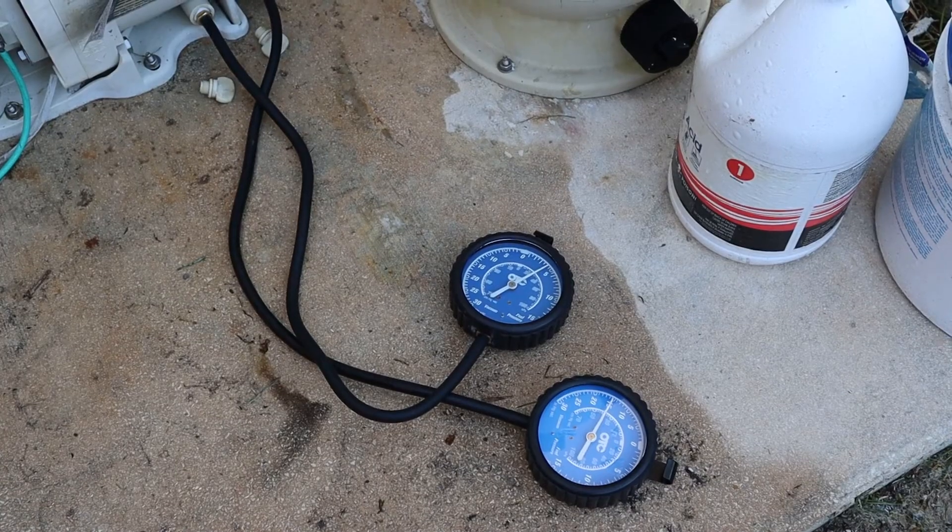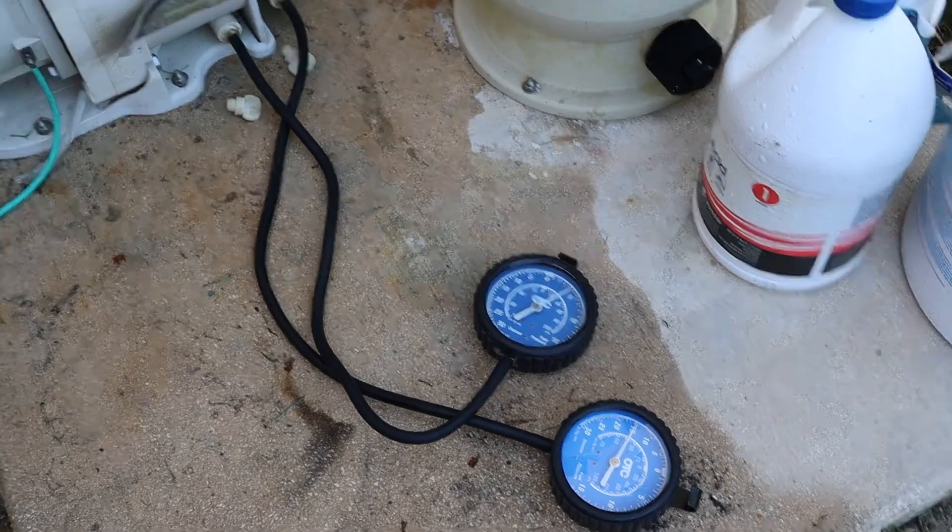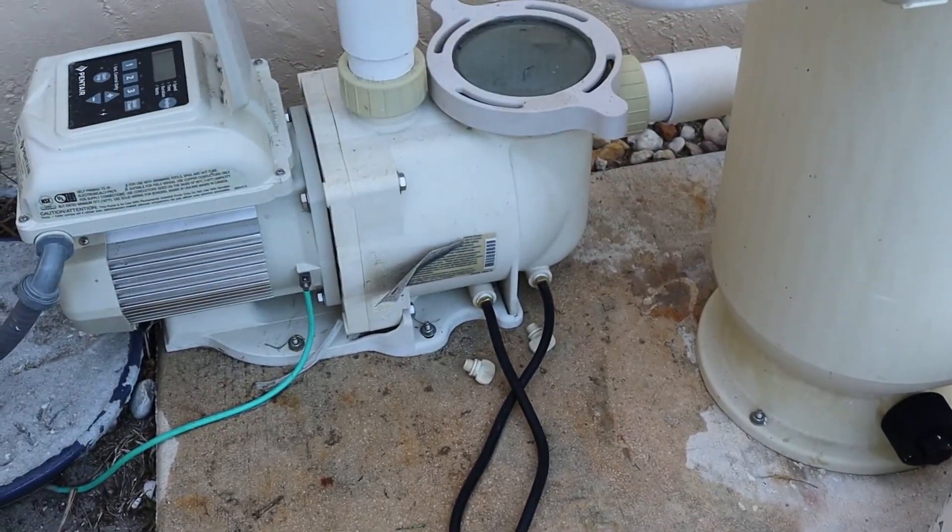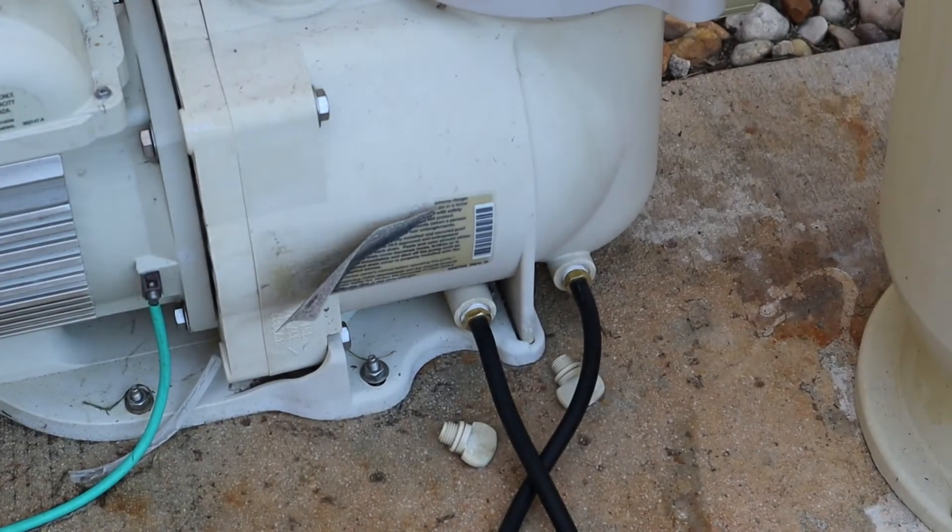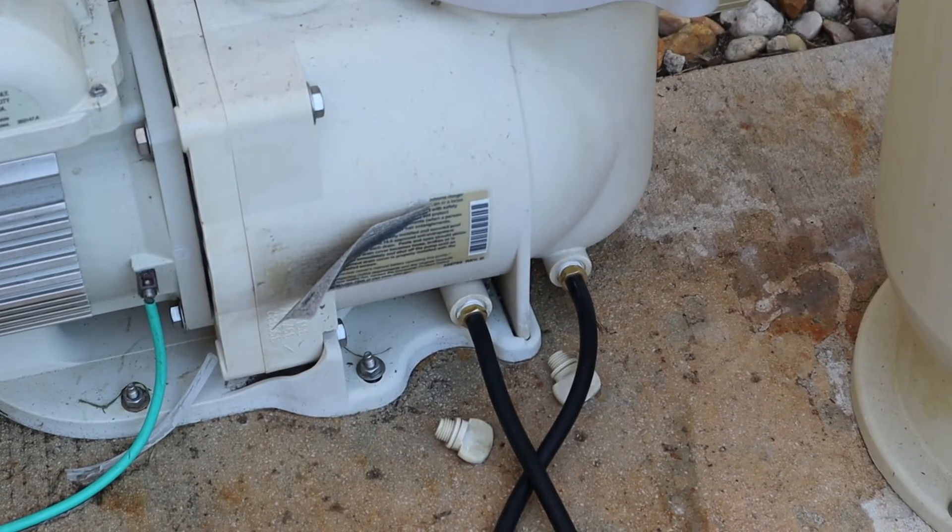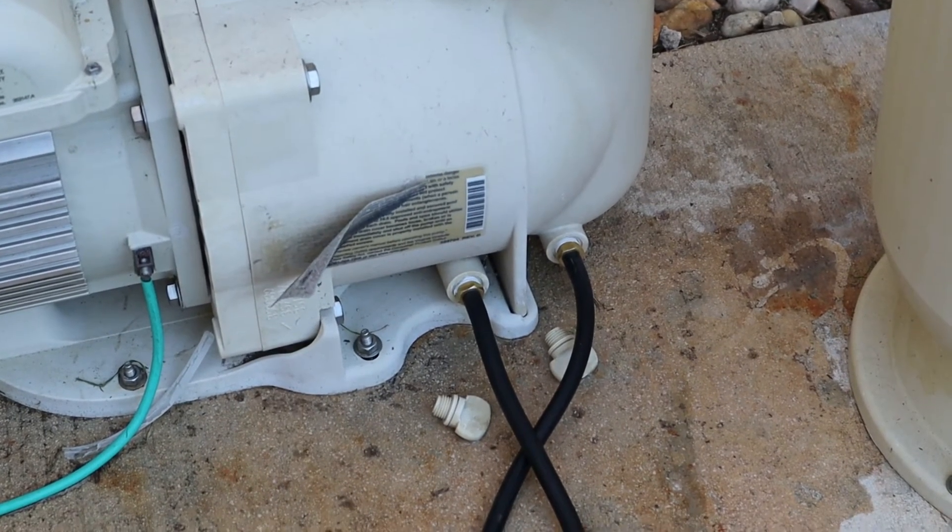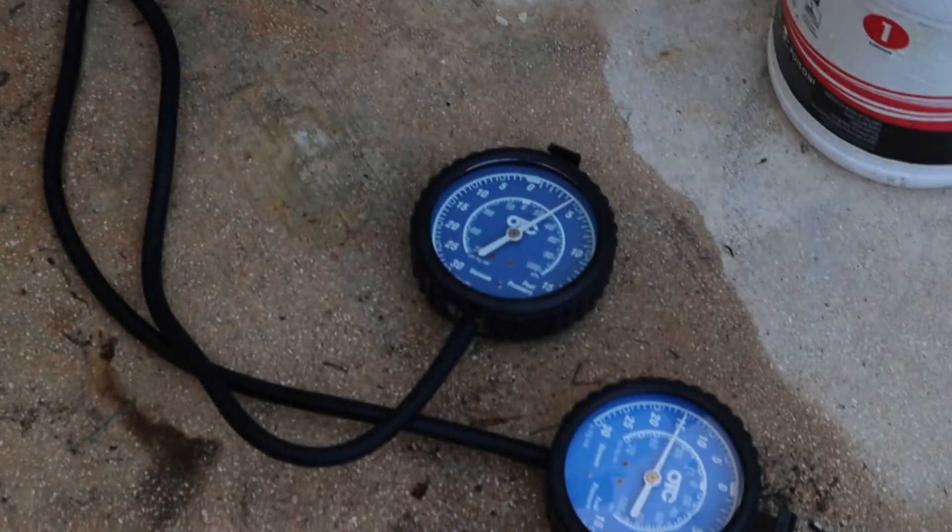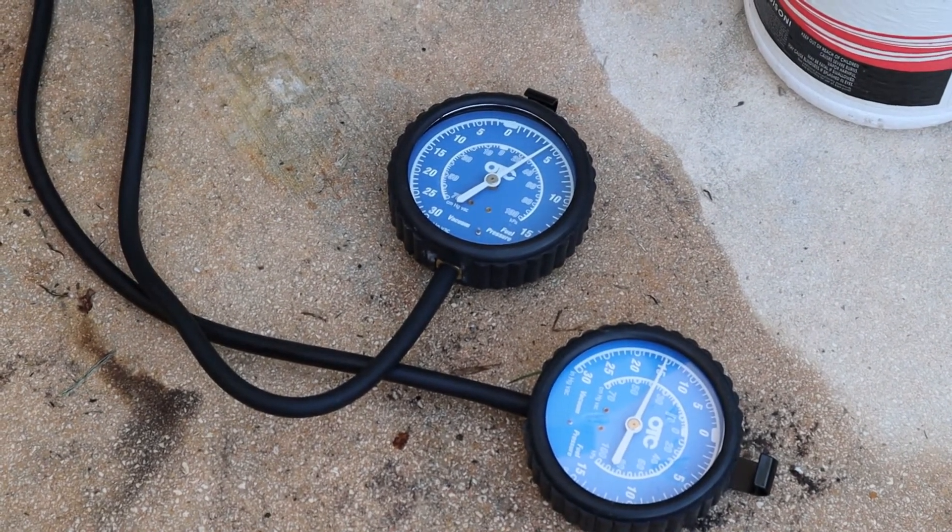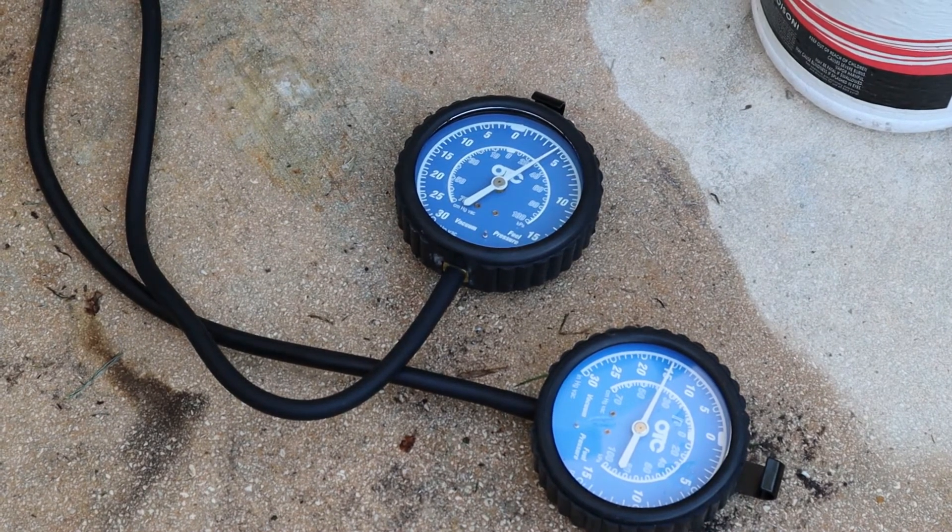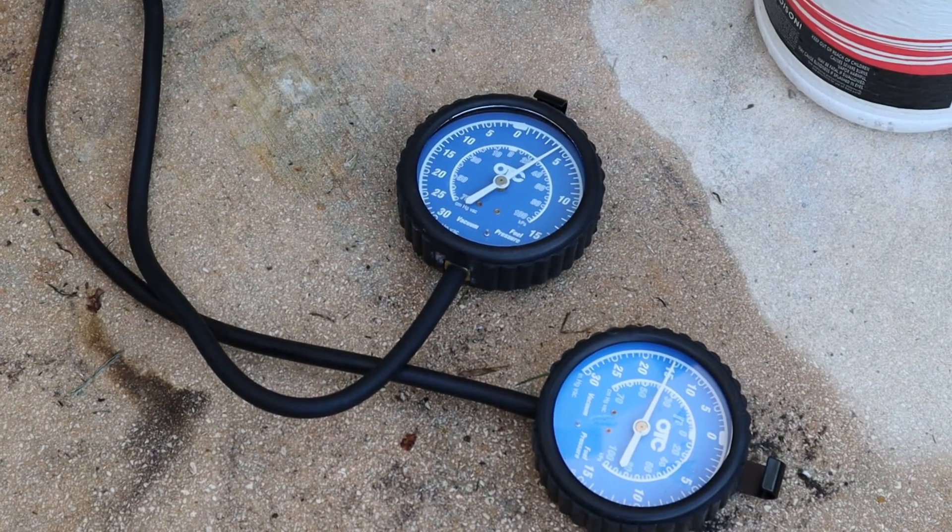I don't know if you noticed how shaky those needles were, but there was a lot of air getting in around those ports. I took them back out and put Teflon tape around the pipe threads. That resolved the problem. Now the needles are much steadier. Let my time wasted save you some time. Wrap the threads with Teflon tape.